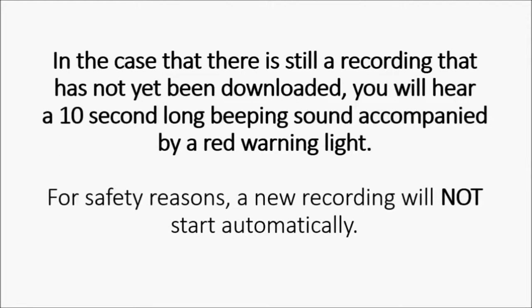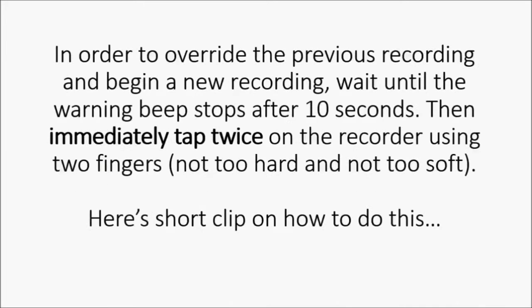In the case that there is still a recording that has not yet been downloaded, you will hear a 10-second long beeping sound accompanied by a red warning light. For safety reasons, a new recording will not start automatically. In order to override the previous recording and begin a new one, wait 10 seconds for the warning beep to stop, then immediately tap twice on the recorder using two fingers.